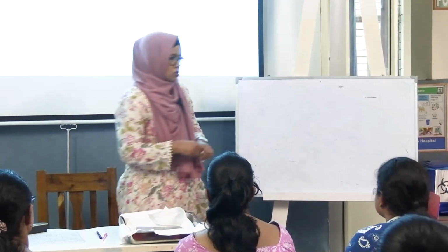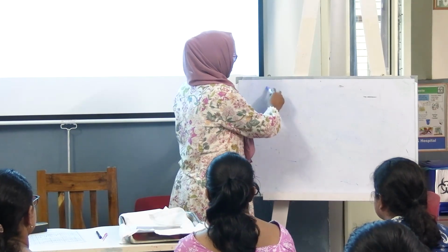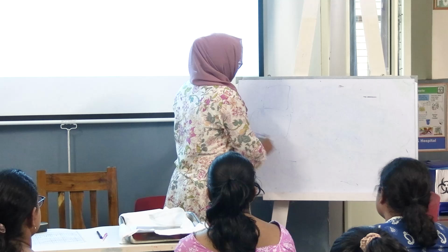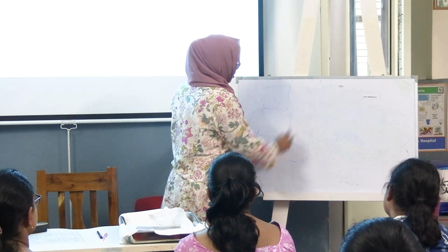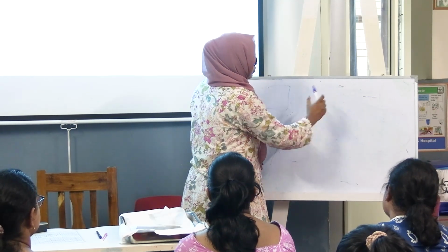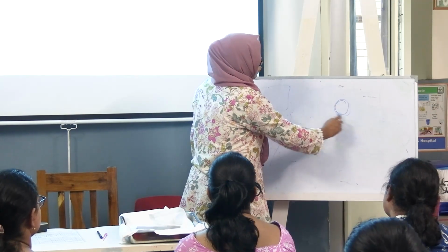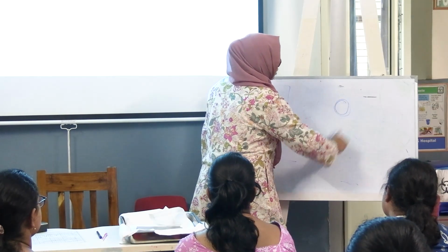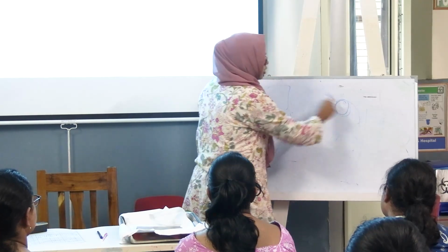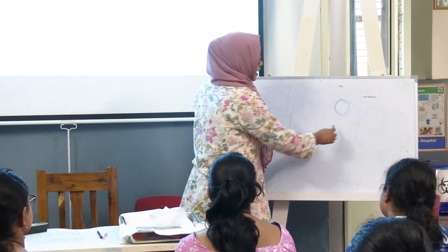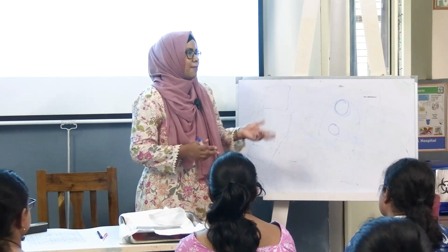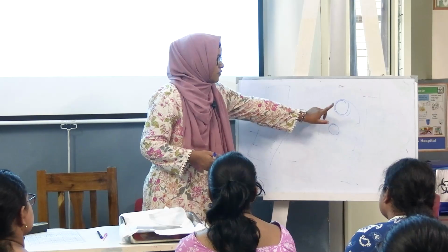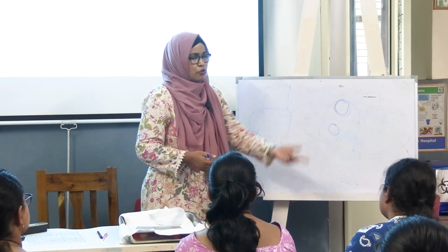Later on, I will show you the CTG machine which is in the labor room. There is a cardiotocograph machine, a monitor, and paper tracing coming out through it. And there are probes. One is the toco probe, which is put over the fundus of the patient to monitor the uterine contraction. The other is the cardio probe, placed over the fetal heart sound where it is best audible. Many times the toco probe is only one, but cardio probes can be two for twin pregnancy.